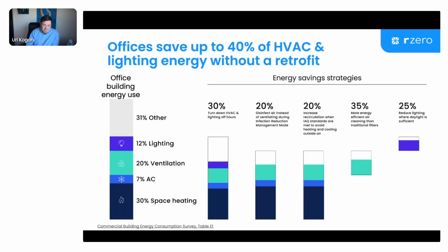But there's another approach you can use to calculate the amount of ventilation required, which is based on an indoor air quality measurement. In order to do that, of course, you need to be measuring it. And to oversimplify this a bit, many buildings are often over-ventilating relative to acceptable indoor air quality. So if you can reduce the ventilation, and reduce the amount of heating and cooling you need to do of that outside air, again, you're going to deliver significant savings. Now, in order to do this, you have to be measuring indoor air quality continuously and adjusting the HVAC. And as I already mentioned, that also will give you additional LEED points.